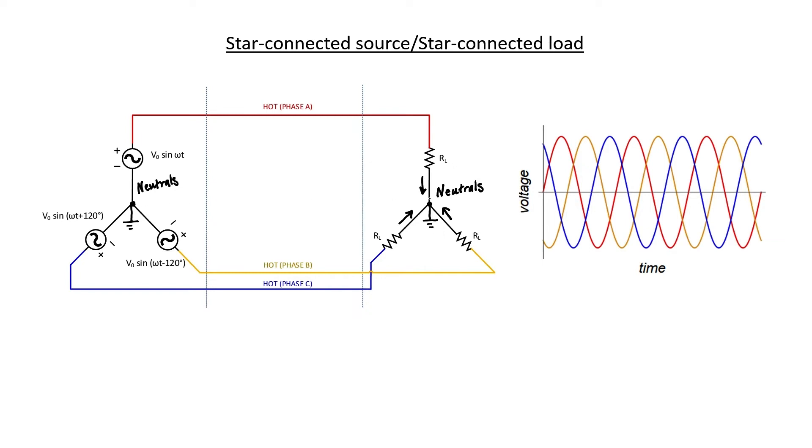In order to get rid of the long neutral wire between the turbine and the star point of our load, the neutrals at the three loads must be connected and the loads must be balanced. Now what do I mean when I say that the loads need to be balanced? If that resistor were a little bit lower or a little bit smaller than the other two resistors here in the star, it means that there would be less of a voltage drop across that resistor. It would cause the neutral point to float above the ground. The voltage drop across the two other resistors would increase. Normally in a power distribution system, you want stable voltages. You don't want the voltage coming out of the wall to rise or fall if somebody in another building or another room plugs in something that's going to use up some of the power. Grounding the neutral point helps to stabilize the grid in that sense. Systems can normally handle a small amount of imbalance, but generally in a three phase power distribution system, it makes a lot of sense to try to have equal current flowing through the three phases.